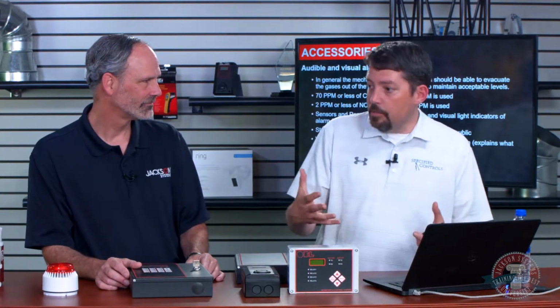Okay. All right. So moving on from sensor height, audio and visual alarms. We're gonna circle back around. We talked all about it. Audible and visual alarms. I'm gonna make this really simple and try to move forward here a little bit. As far as audio and visual alarms, virtually every engineer out there is going to say sensor or system with audio and visual alarm. Every manufacturer that makes gas detection panels and sensors has an audible and visual alarm in the sensor and on the panel.